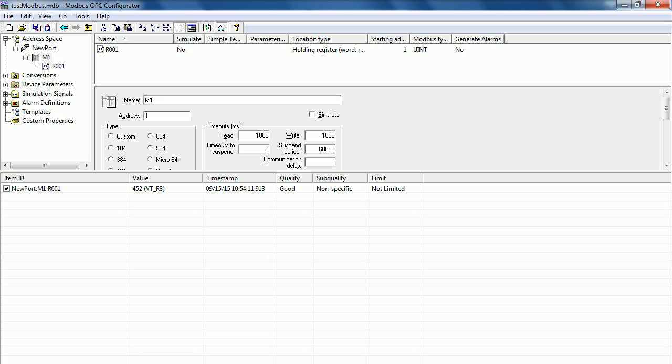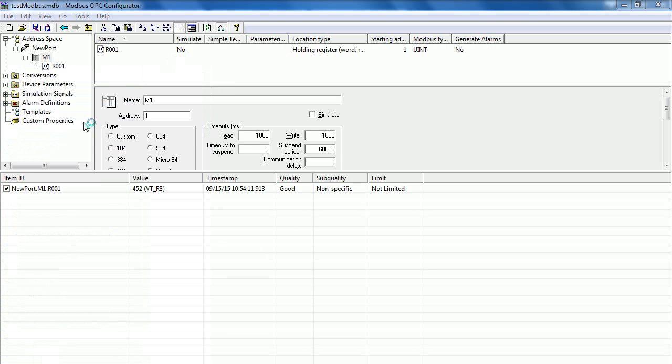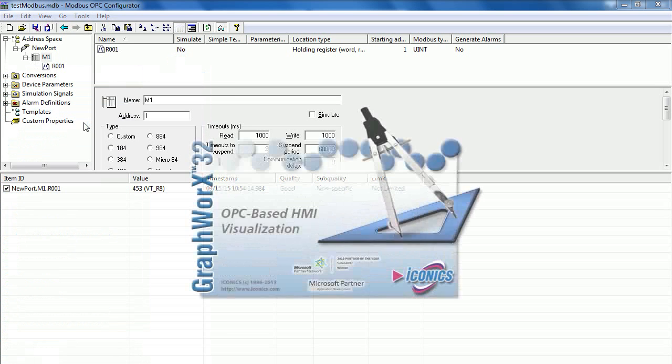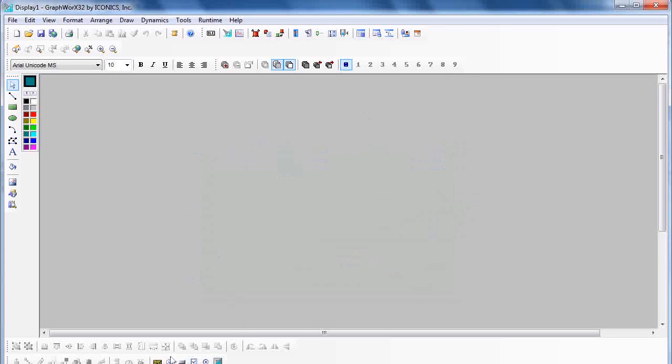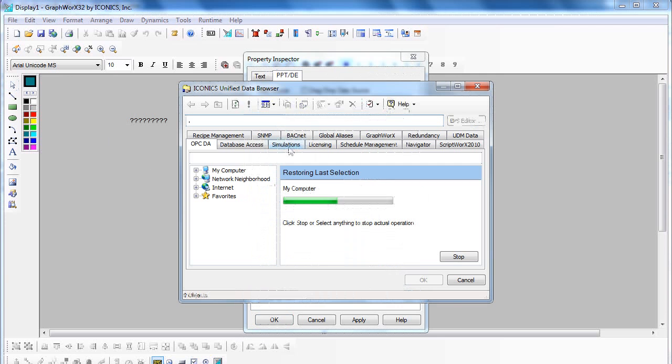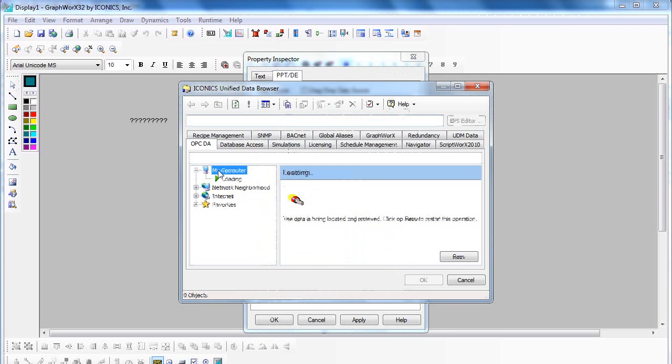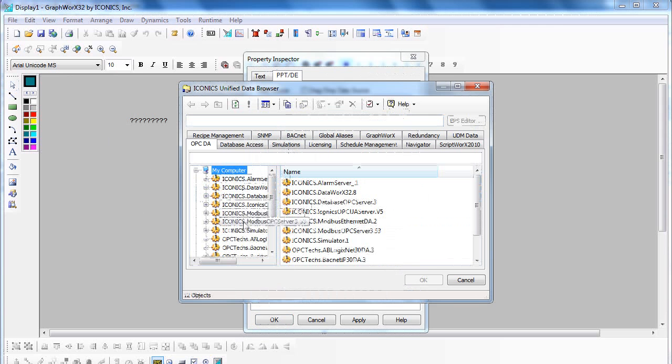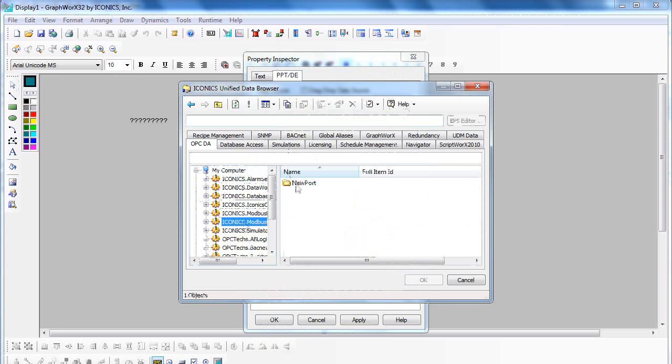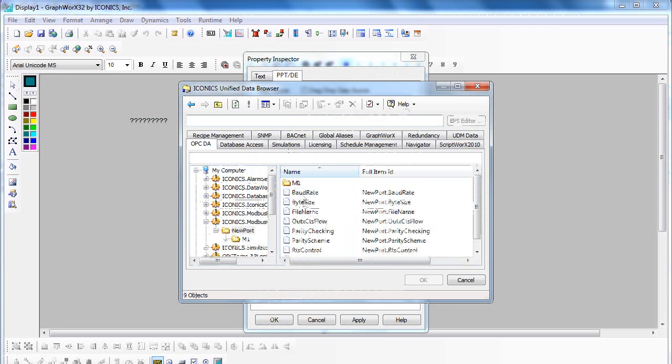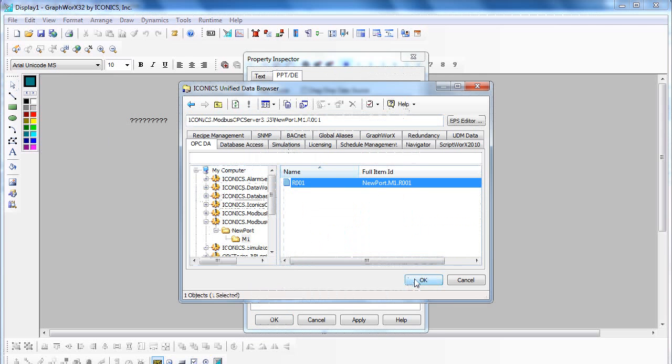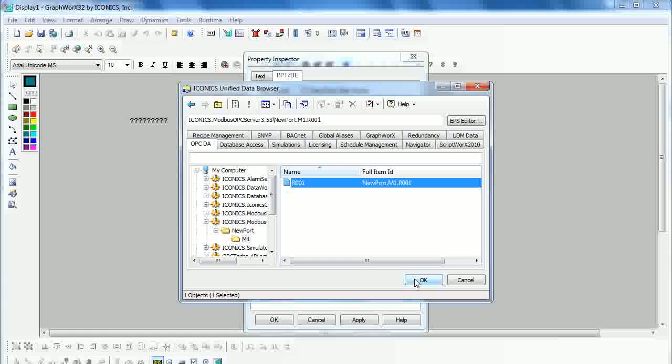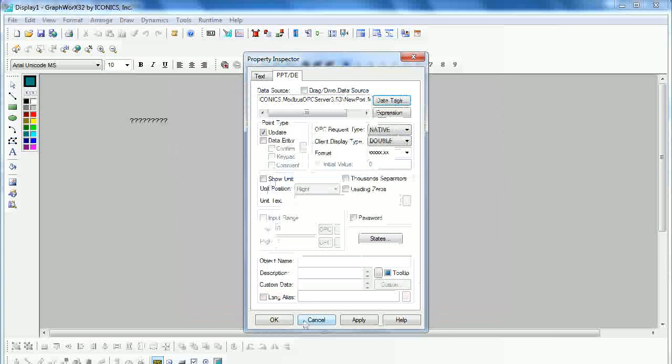To test with Genesis 32, open Graphworks 32 and then place the process point into the workspace. Click on Data Text. Browse to your OPC Server under My Computer, Iconics Modbus OPC Server, and select the OPC Tag. Then click OK.